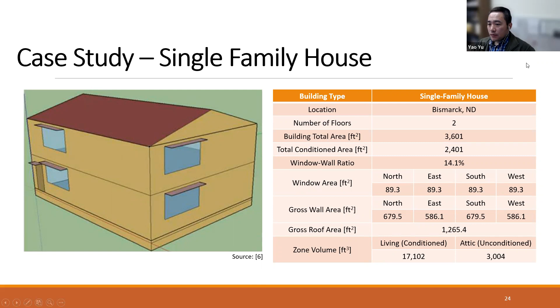In the case study, we compare a heat pump system used in the house with two types of underground heat exchangers. The double layer underground heat exchanger is shown with five slinky heat pipes at two layers: one buried right below the ground surface, called the upper loop, and the other buried underground at a depth of 8 feet. Five inches of rigid insulation are placed between them to minimize the interference between them.